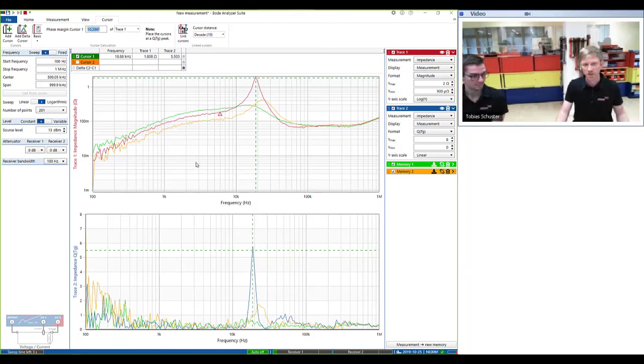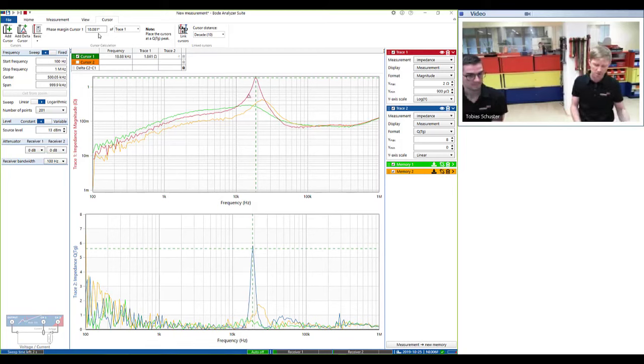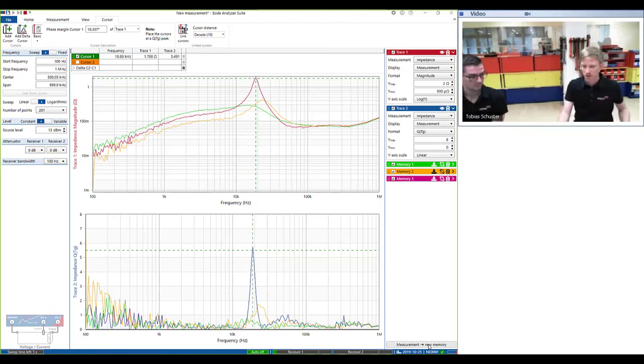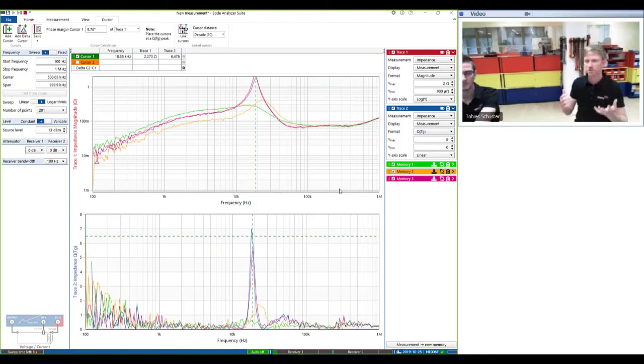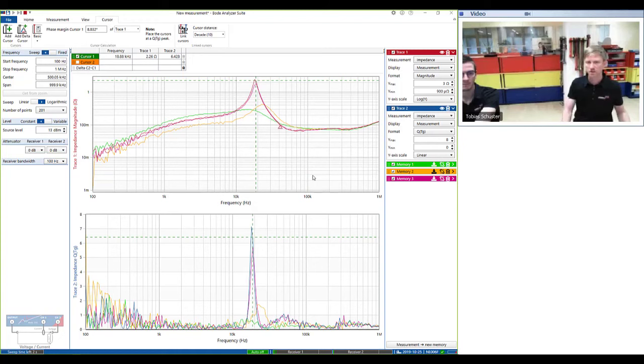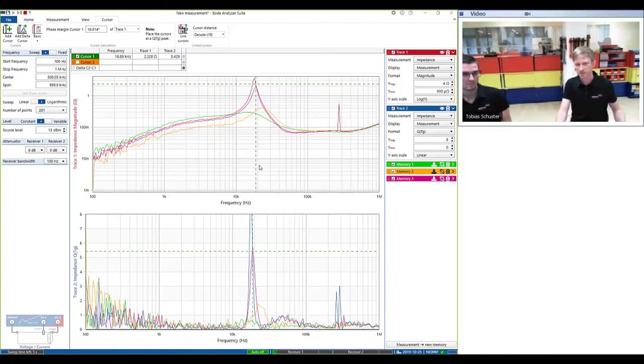And the phase margin calculation at the peak in the Q is now indicating a phase margin of roughly 9 to 10 degrees. And that matches exactly what we have seen in the previous webinar, where the loop gain measurement did show 9 degrees of phase margin at 20 volts input and 1 amp output current. So the advantage of this non-invasive stability measurement is that you don't need to break the loop, you don't need to insert an injection resistor, you don't even need to find access to the loop. You can just access the output of the regulator, and if the phase margin is too low, there will be a peak in the output impedance that you can use to estimate the phase margin.